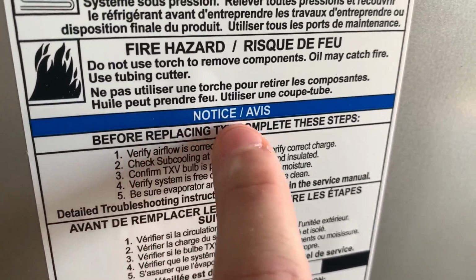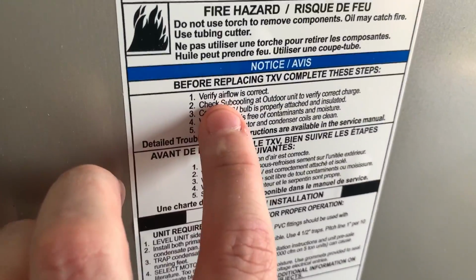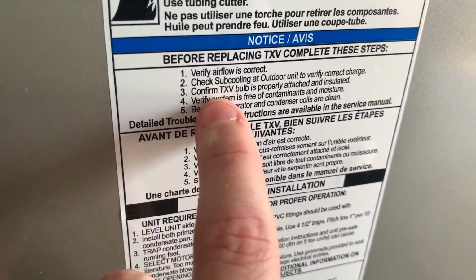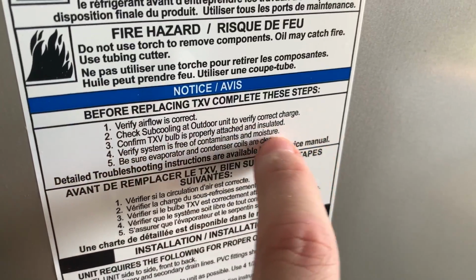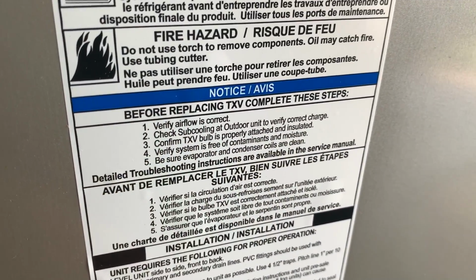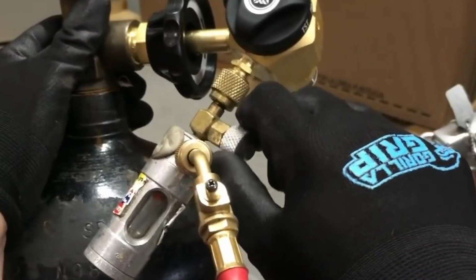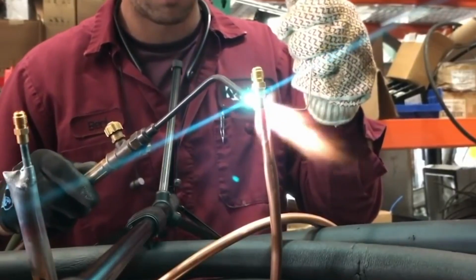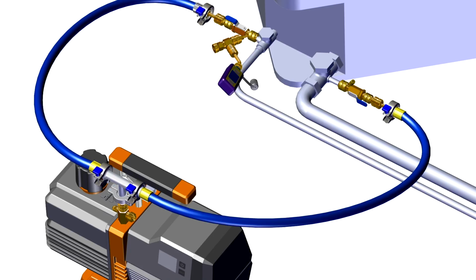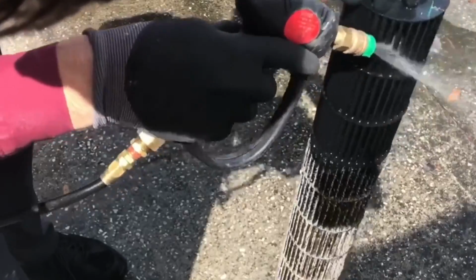I think this is kind of cool note on here. It talks about before replacing the TXV, complete these steps. This is right on the air handler panel. Verify airflow is correct, check subcooling, confirm TXV bulb is properly attached, verify system is free of contaminants and moisture, and the only good way of doing that is by doing your proper procedures to begin with, flowing nitrogen while brazing, and then doing a proper evacuation, and then make sure everything's clean. I would also add blower wheel to that.